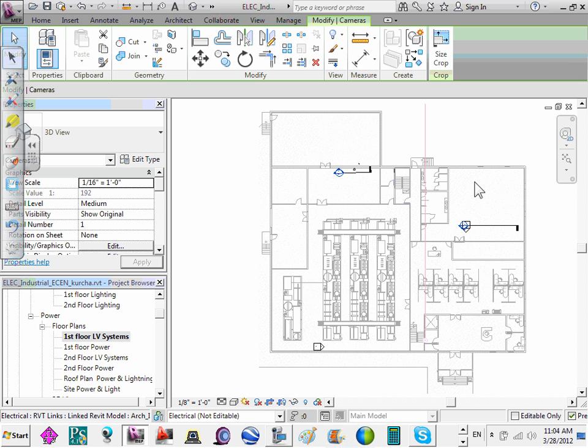Other than that, we talked about the security system. If they have a locked door, say for here, and there is a fire alarm system, if this is a path of egress, we would have a control module to drop the power. They have to be fail safe, so that we can shut off the power to those doors so they can get through the egress. They might have door holders here. You have to have smoke detectors: if it's more than 24 inches down from the ceiling, you have to have a smoke detector on each side. If it's under 18, you just have to have it on one side. So you're going to have a smoke detector that's going to control that door. It's not going to go into alarm. It's just going to be supervisory because it's for that function only. It's door release only. And you're going to have a control module on each door holder.